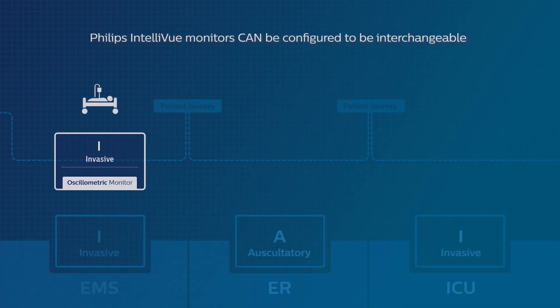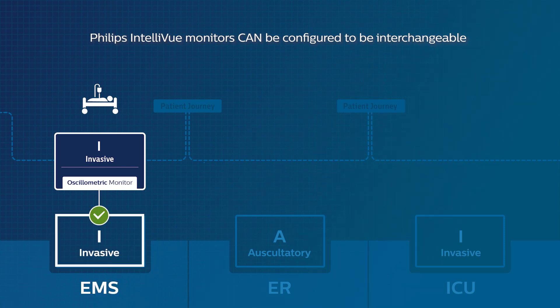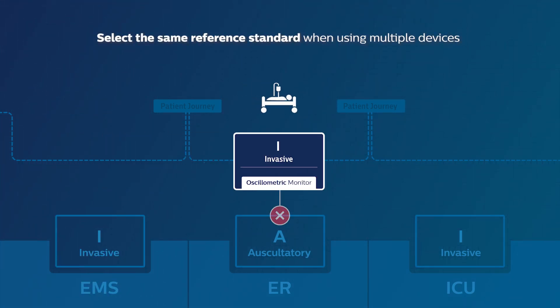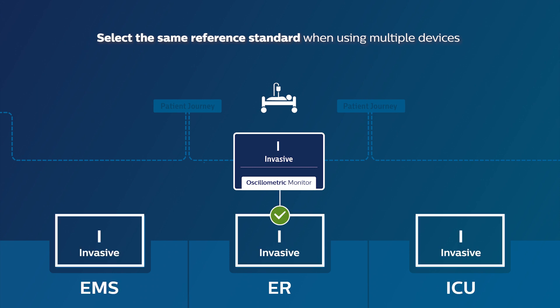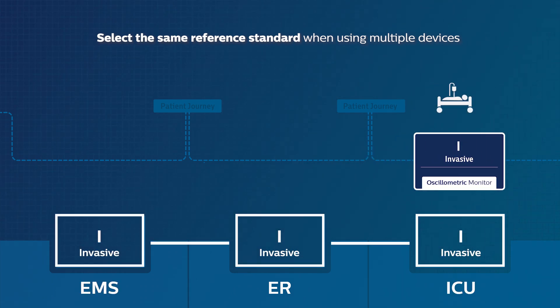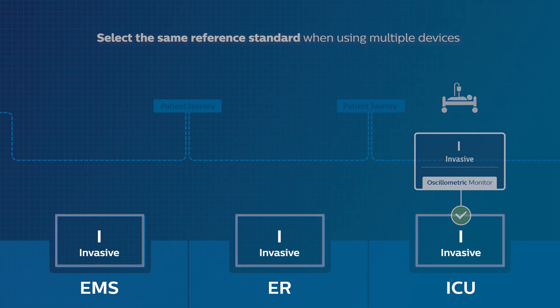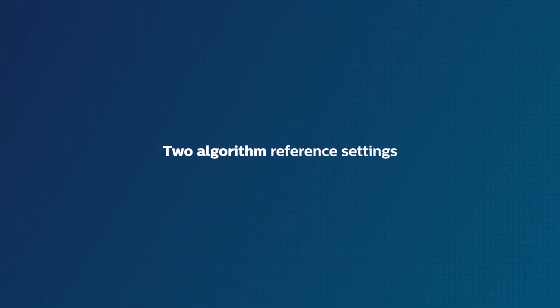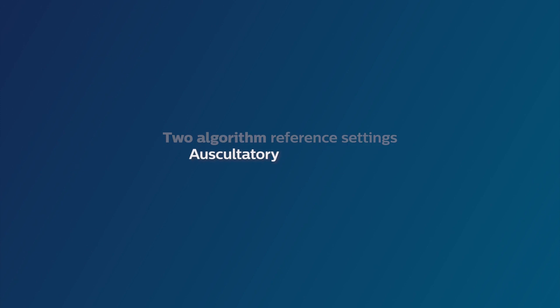Philips IntelliVue monitors can be configured to be interchangeable by selecting the same reference standard algorithm on all devices. IntelliVue users can choose from two algorithm reference settings: auscultatory and invasive.